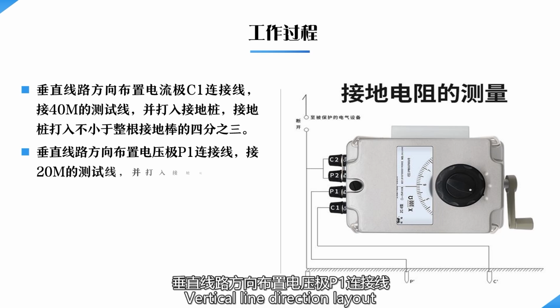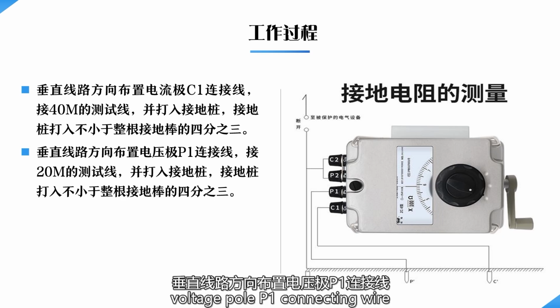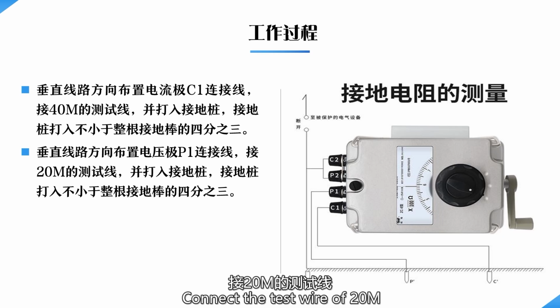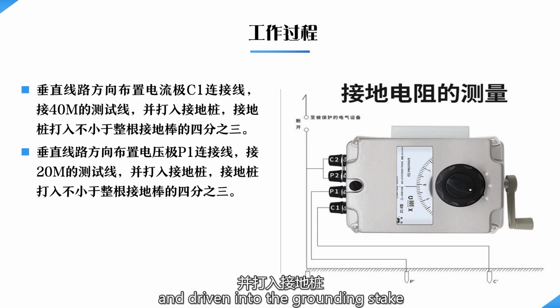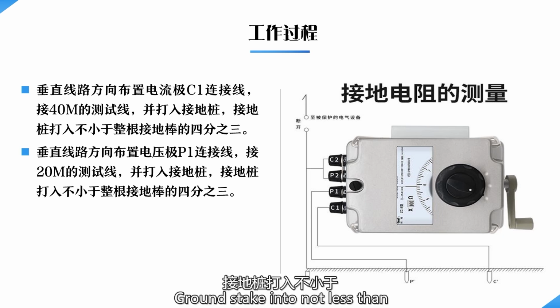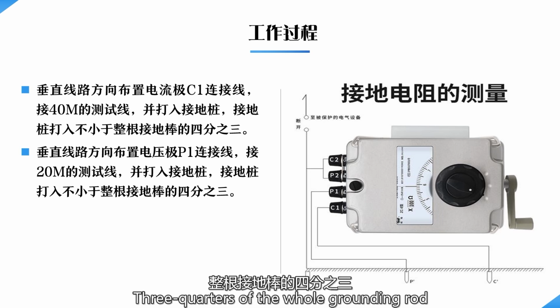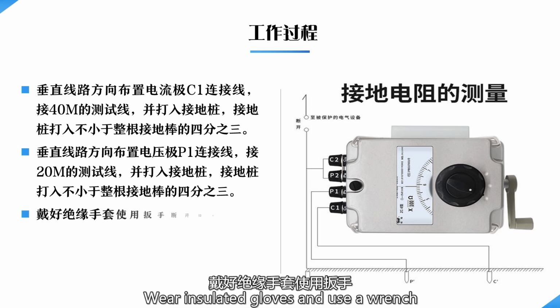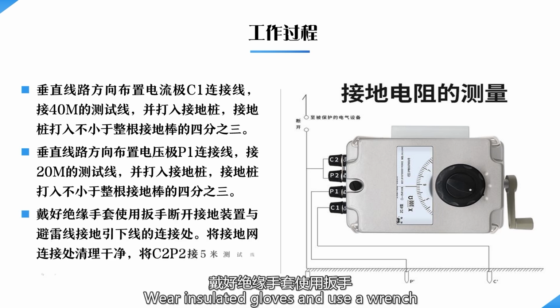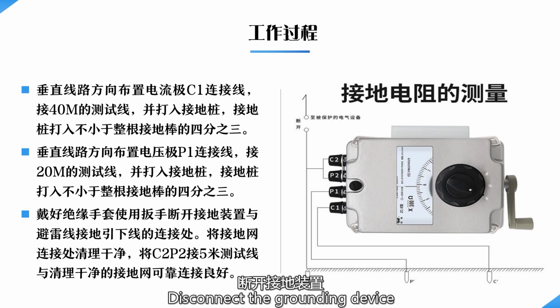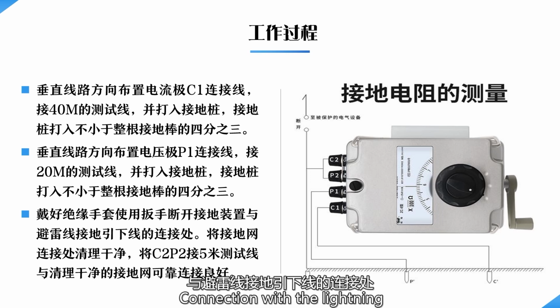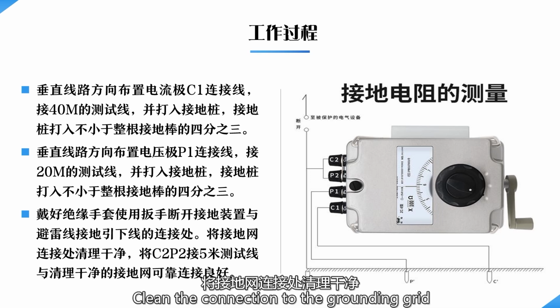In the vertical line direction, lay out the voltage pole P1 connecting wire. Connect the 20 meter test wire and drive in the grounding stake, not less than 3/4 of the whole grounding rod. Wear insulated gloves and use a wrench. Disconnect the grounding device from the lightning conductor's grounding connector. Clean the connection to the grounding grid.